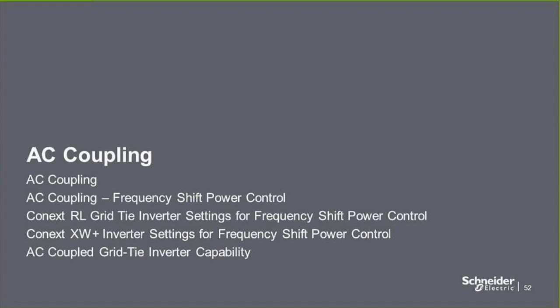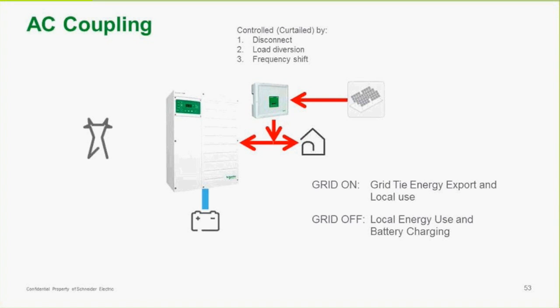So now we're going to talk a bit about AC coupling. AC coupling is done when we have a grid-tied inverter tied to the output of the XW Plus. Grid on: grid tie, and energy export and local use. Grid off: local energy use and battery charging. This grid-tied inverter is controlled by the output of the XW Plus. If the battery's fully charged and the loads are being powered and there's excess power, there is a chance that this will continue to overcharge the batteries. So the output of this inverter has to be curtailed, either slowed down or shut off altogether.